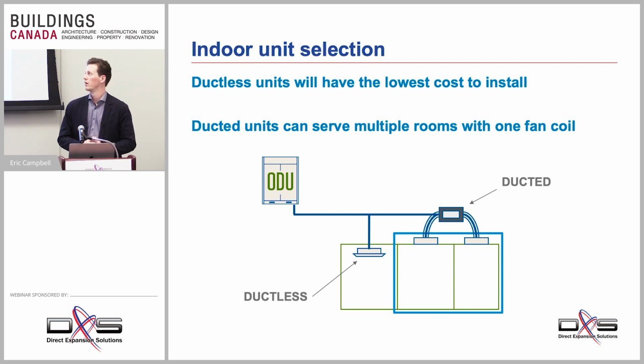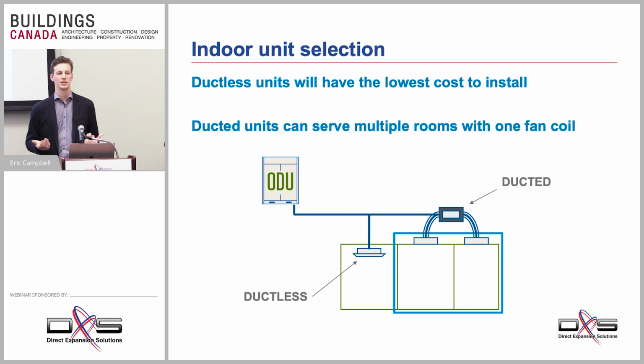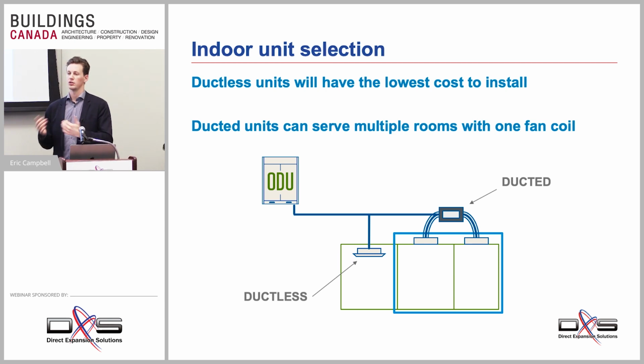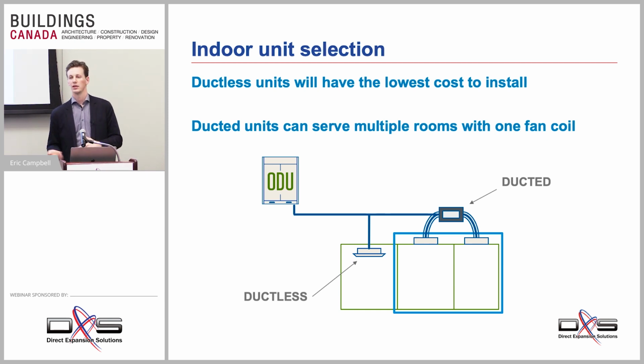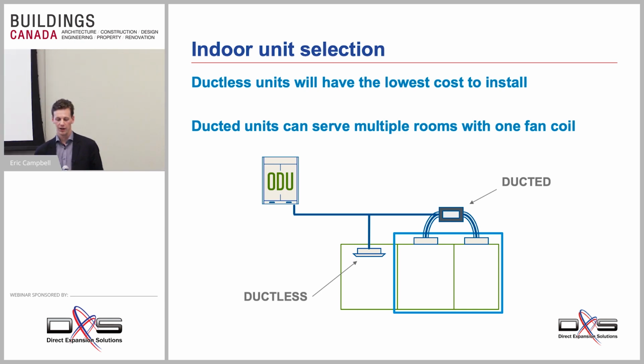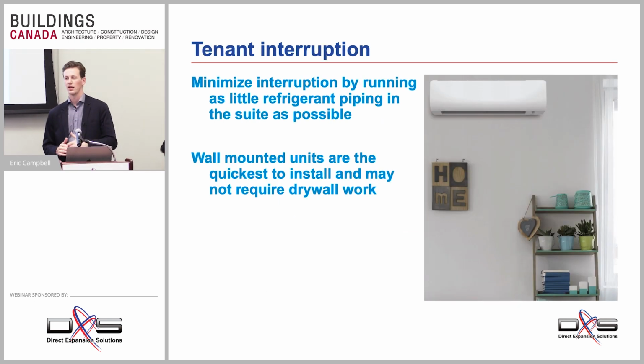Going back to a ductless unit, if you want to use a ductless unit but you've got multiple spaces, you might end up needing one wall-mounted unit in each space, and that can drive up your cost, and it can also increase the piping cost and that sort of thing. So that evaluation is important, and there's no right answer. It's all going to depend on the specific project. Typically, multi-unit residential buildings that do have electric baseboard heat don't have the space to put a ducted unit, and so we see a lot of them going to the wall-mounted solutions.